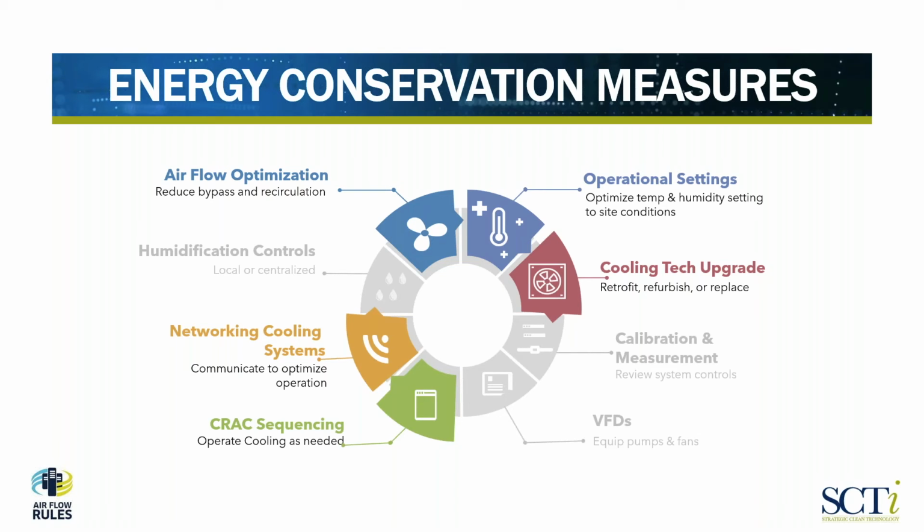And by the time we're done with our cooling optimization program, we can show that customer that that site can clearly operate, and operate much better, on 5 CRAC units or maybe even 4 CRAC units, which means that they don't incur that additional cost for new capital equipment, and they've also saved a considerable amount of money.